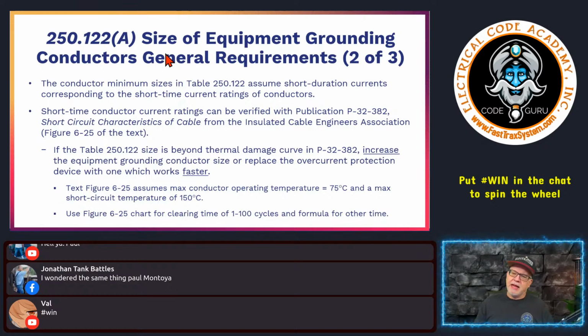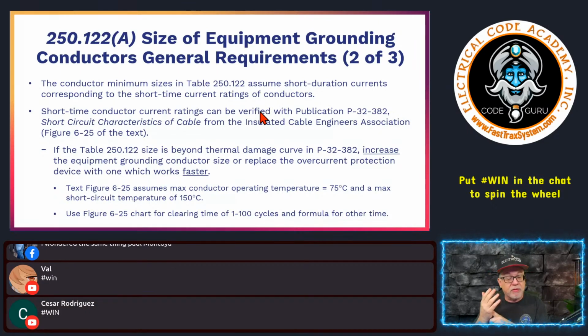All right. Next, it says the conductor's minimum size in table 250.122 assumes short duration currents corresponding to the short time current ratings of the conductor. I don't know if you know this or not, but like a bare 14 can handle thousands of amps of current quickly, momentarily, very short. Okay, so people don't understand the concepts of it, but this is a very short, quick duration within the trip curve of an overcurrent protective device. And so again, one of those things to keep in mind is we are sizing equipment grounds because we are trying to clear an overcurrent protective device, right? Under the ground fault component, okay?